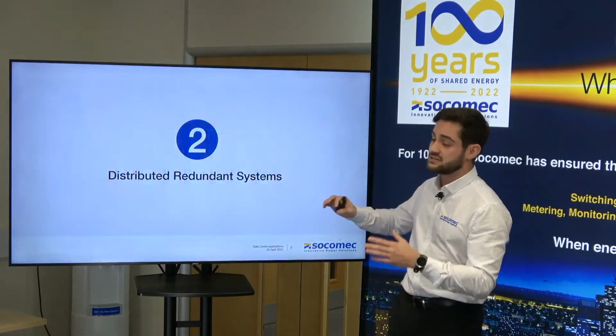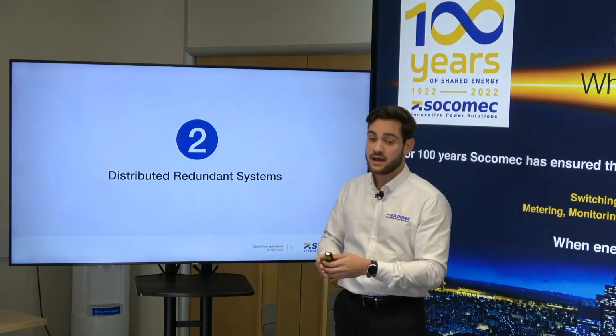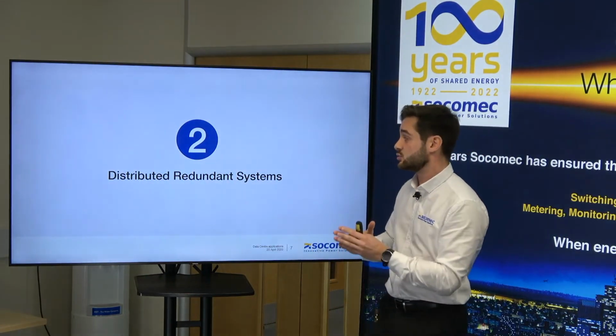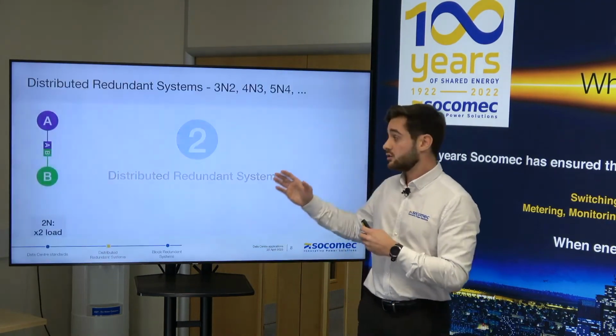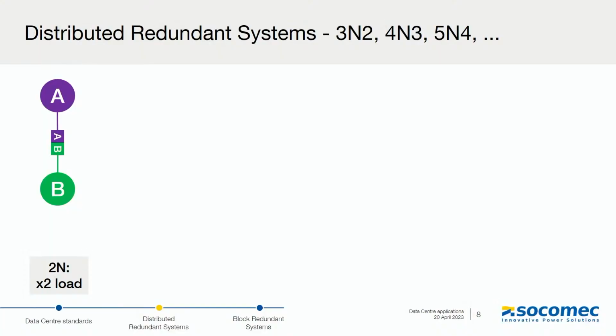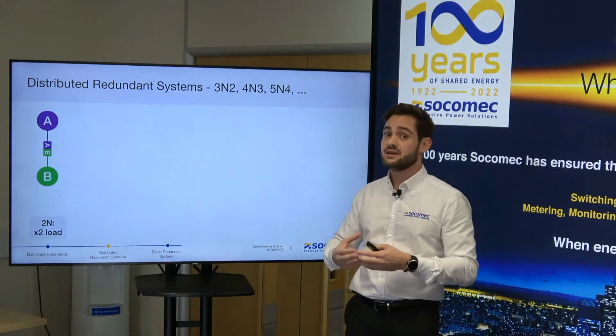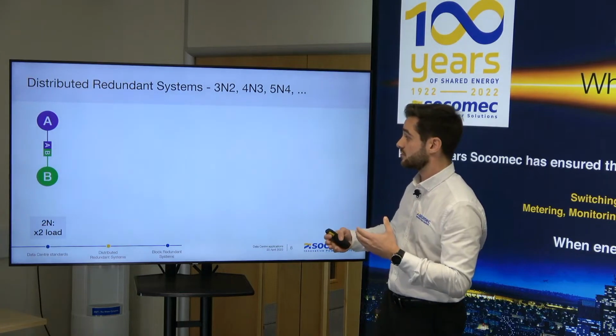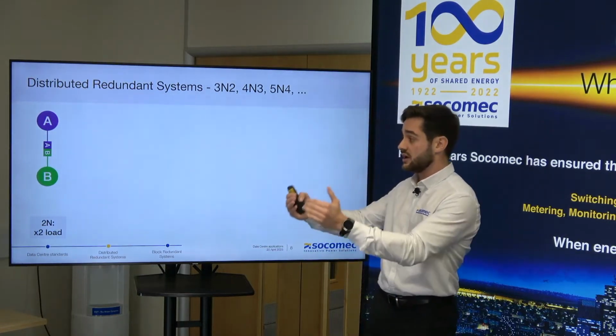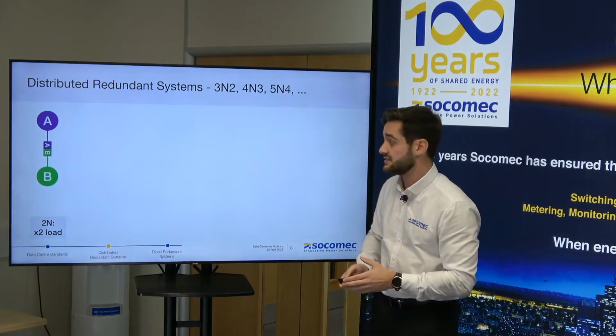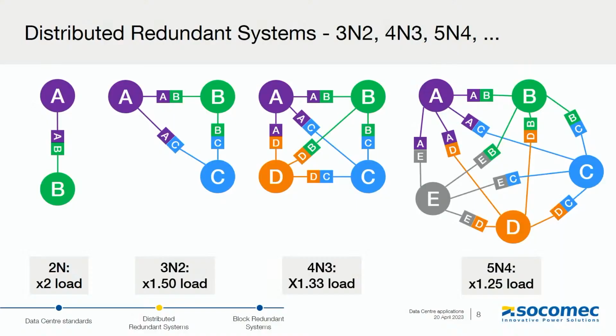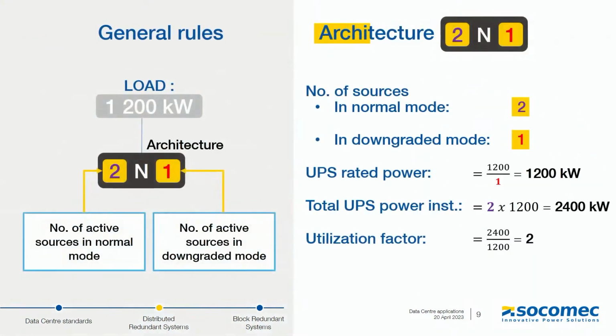So now we've understood about the tier classification and the 2N system. Let's go a little bit further and understand the distributed redundant systems. 2N is part of this distributed redundant system. As we said, we've got a load, and basically the UPS systems need to be twice the load. So in big data centers with big loads, it can be very expensive. So there are some alternative solutions to reduce the cost and reduce the size of the UPS system installed. As we can see here, we mentioned 3N2, 4N3, and 5N4. But what does it actually mean? Let's review it here in more detail.